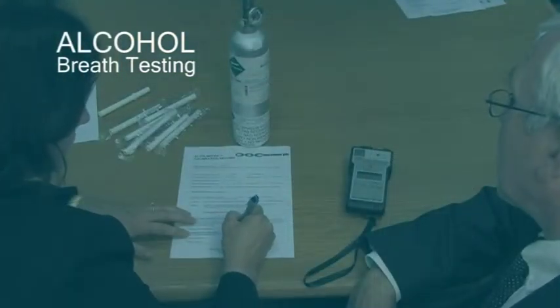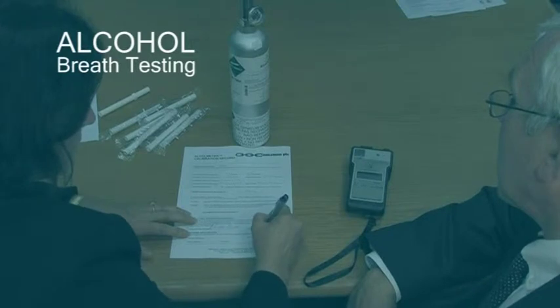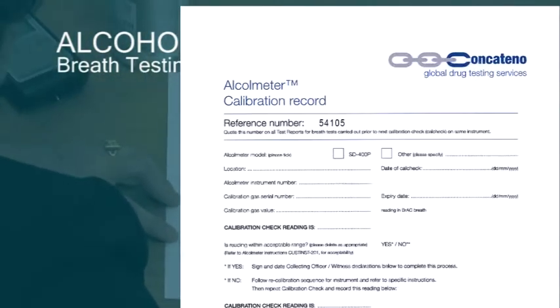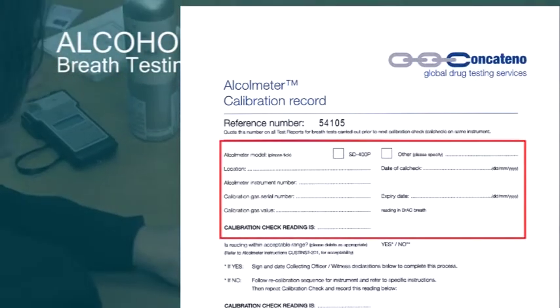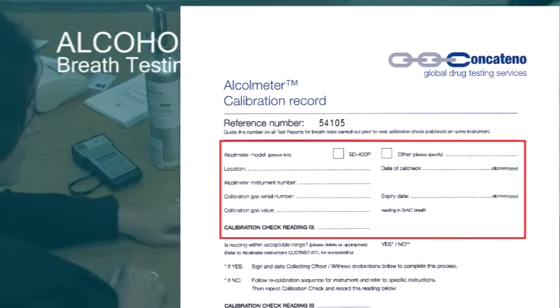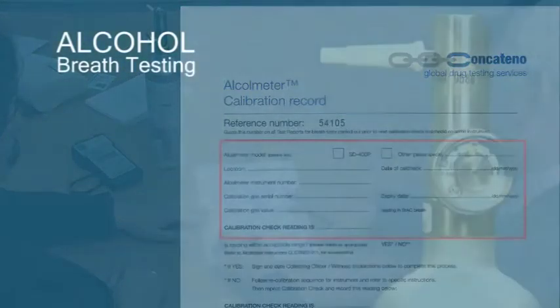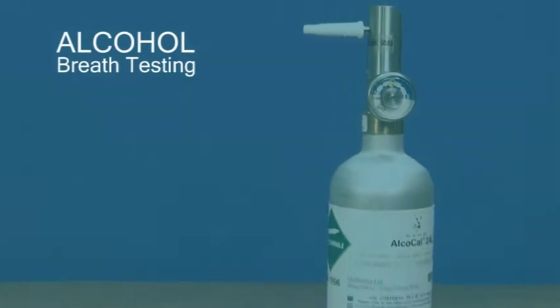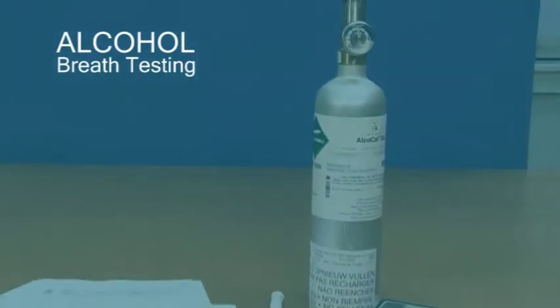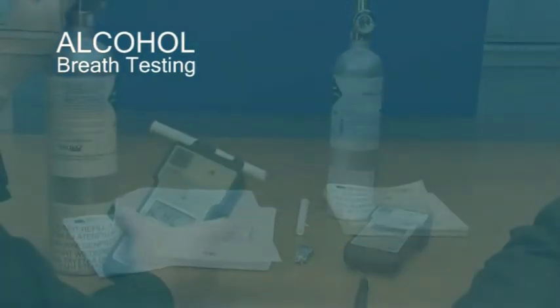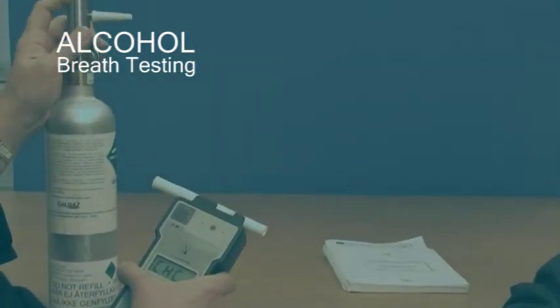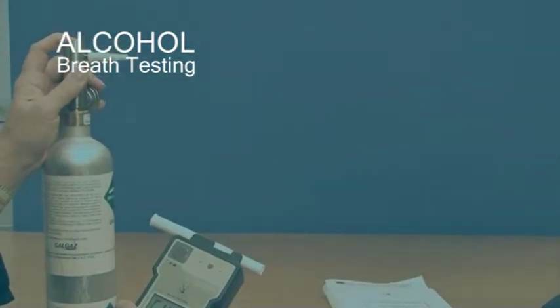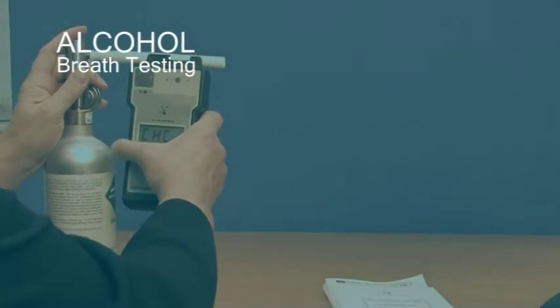Have your witness present and explain that you want them to witness the check to demonstrate that the machine is working properly. Use the calibration record and complete all the information relating to the machine and the calibration gas being used. Have a flat surface to stand and steady the cylinder, as both your hands will be occupied. One holding the SD400, the other pressing the flow button on the cylinder.